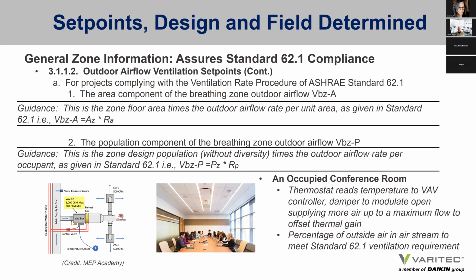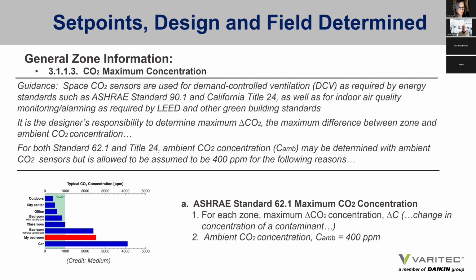It also shows, for example, if you have an occupied conference room, how the VAV box will actually control. This thermostat reads the temperature and sends it to the VAV controller for the damper to open to allow more airflow when a conference room loads up with occupants, and to throttle back and restrict airflow in the event the conference room is partially full or empty. So you can actually regulate the airflow to the space so that the amount of airflow is appropriate to the demand of the zone, so energy is not being needlessly consumed to overcondition the space when it is not occupied.